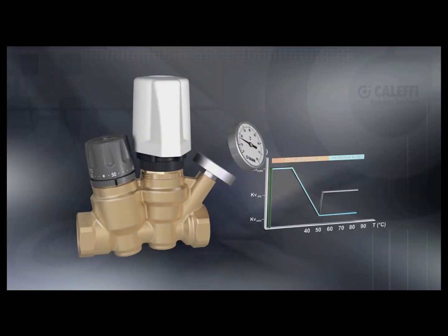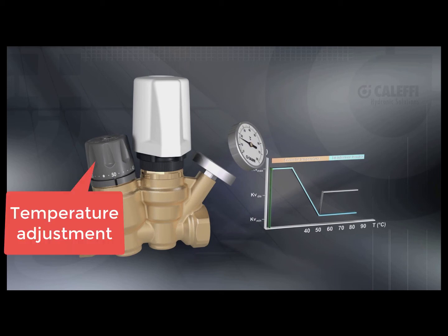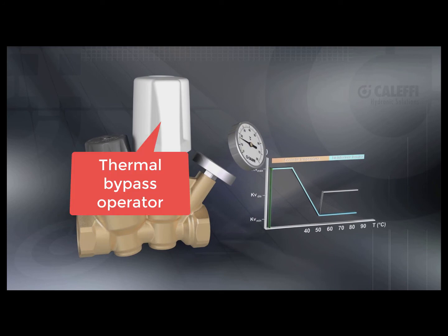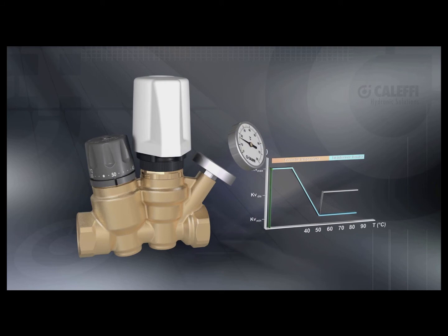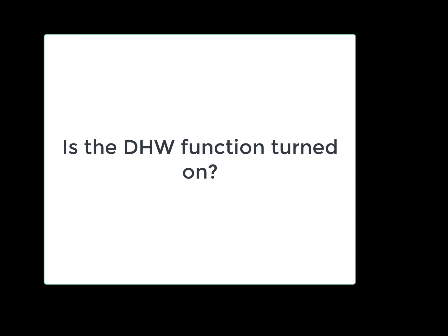This is a picture of the Caleffi Series 116 thermal balancing valve. The knob on the left is used to set the temperature at which the valve will start shutting down. The white solenoid valve will bypass that thermal setting and allow full flow to go through the valve during scald sanitization. And the thermometer is on our right hand side. This device also comes with an additional check valve that can be piped in series with the valve, but is not required. At this point, I think we should cover some domestic hot water troubleshooting basics.